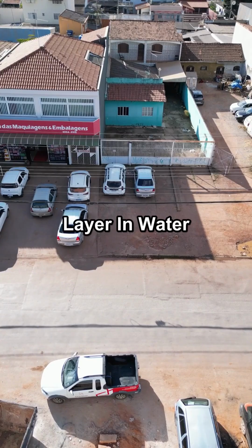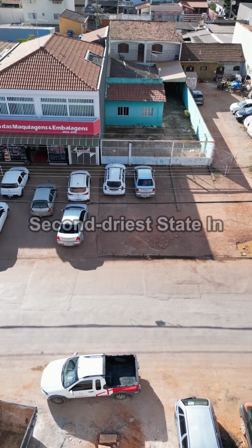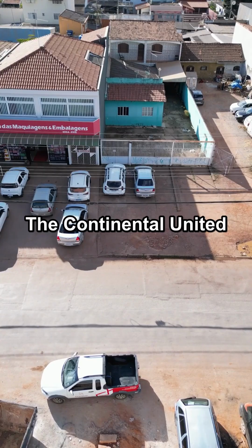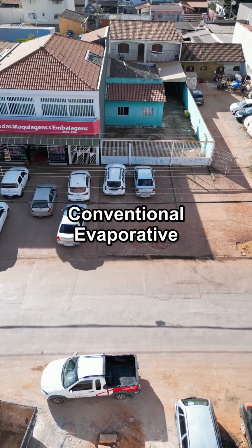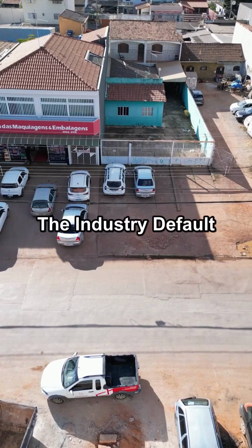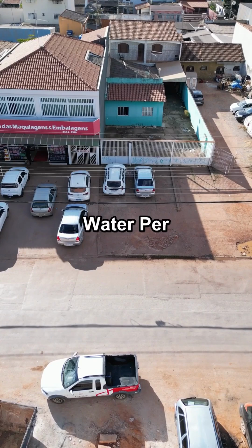Now layer in water, because this is where the Utah location creates a problem the developers need to answer publicly. Utah is the second driest state in the continental United States. A conventional evaporative cooling tower setup, the industry default for large-scale facilities over the past 2 decades, consumes roughly 1.8 liters of water per kilowatt-hour of IT load removed.